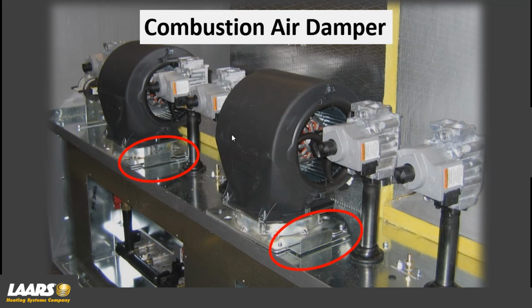Now, also on these blowers, we'll have a combustion air damper. So when we go through combustion setup today, this will need to be adjusted. For combustion setup, for all of these products, you'll have to go in and measure and adjust, if needed, your gas pressure for each valve with a combustion analyzer. Now you're going to measure for CO2, and the only thing left is to adjust your air shutter. If you have a single blower, fine, just open or close it as needed. We'll talk about that. However, if you have two blowers, you want to open both blowers equally.